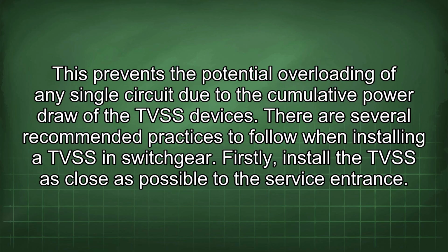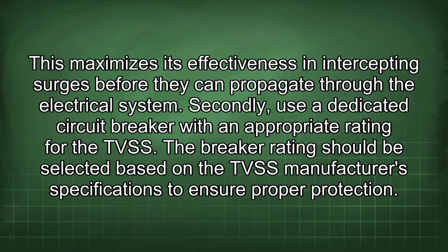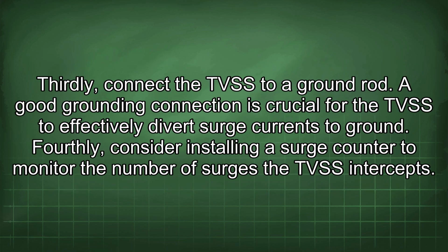There are several recommended practices to follow when installing a TVSS in switchgear. Firstly, install the TVSS as close as possible to the service entrance. This maximizes its effectiveness in intercepting surges before they can propagate through the electrical system. Secondly, use a dedicated circuit breaker with an appropriate rating for the TVSS. The breaker rating should be selected based on the TVSS manufacturer's specifications to ensure proper protection. Thirdly, connect the TVSS to a ground rod. A good grounding connection is crucial for the TVSS to effectively divert surge currents to ground.